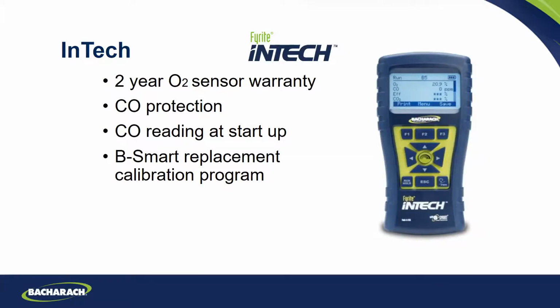Okay, well, that's fine. We're going to tell you later on about calibration on a CO sensor, and you want to calibrate it once a year. It stays rock solid pretty much up there. You put 100 ppm on it or 500, it stays perfectly fine. But down around 0, they kind of move around a little bit.